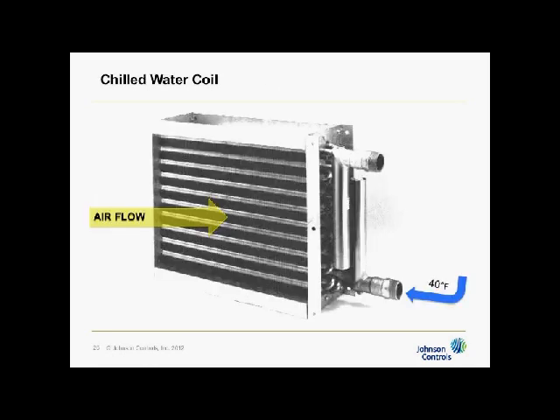When you're in a coil, the airflow goes through the coil. This is the entering air side over here, and I come through the coil to the leaving air side. I want my coldest water, which is here, going in where my coldest air is. So you can see that this pipe is located near the leaving air side of the coil. And this pipe is located near the entering, or the return air of the coil. The return water of the coil, and the entering air. So that, and my valve is usually located on the return side.